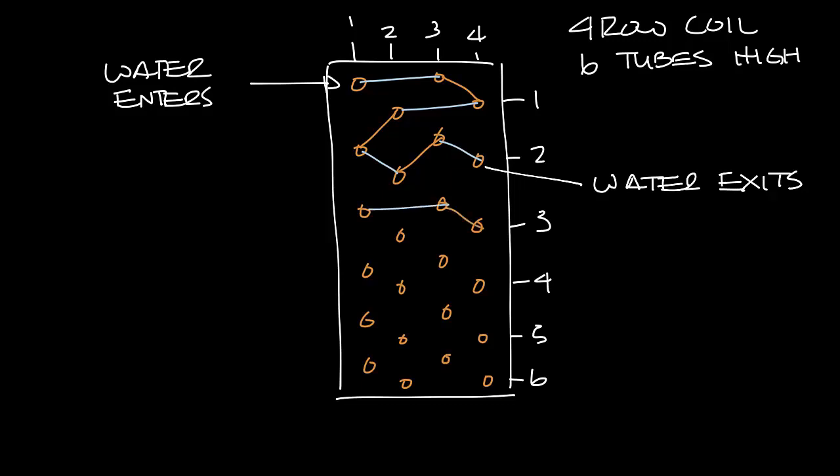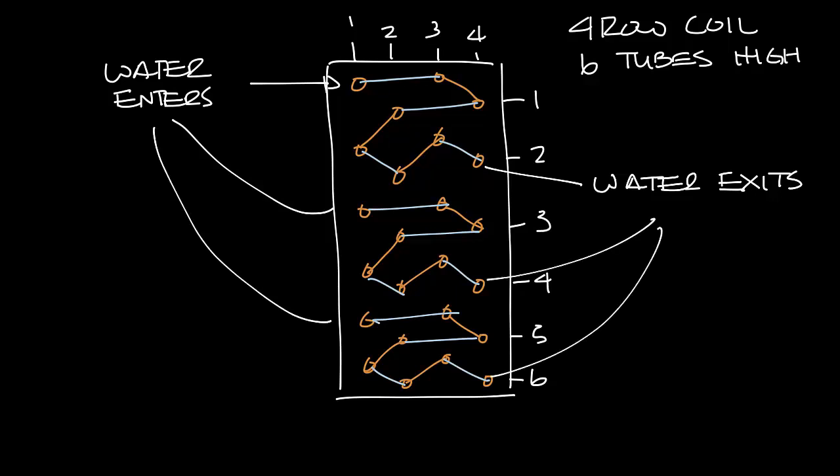So let's draw that for the rest of the tubes. We'll have the same pattern, and then down here on the last set. So what you can see here is that we have three places where the water will enter the tubes in the water coil and three places where the water will exit. So these are places that would connect to the headers, and this makes it a three circuit water coil because we have three connections to our headers.